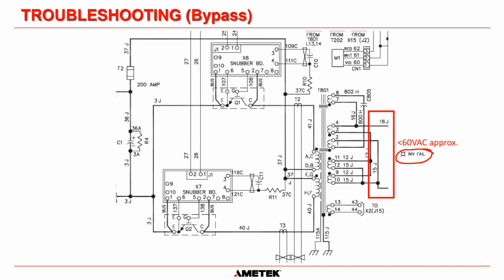If you have the inverter fail light on, then the inverter fail is measuring the output of the system. So this is not square wave fails, which was this one here. This is actually measuring on the output of the system. So we have a healthy square wave going in, but let's say there's a short circuit somewhere. It could even be in the transformer or something out on the load. If it pulls down the voltage to below 60 volts AC, then the system will transfer to bypass. So if you had inverter fail on, that is what happened. And then you'll have to try and figure out why the system went down to 60 volts, which can be quite difficult in truth, but at least you know it's not the square wave or it's not the DC if you have the inverter fail light on the board.